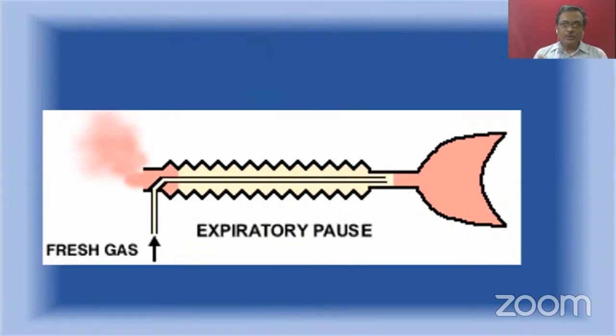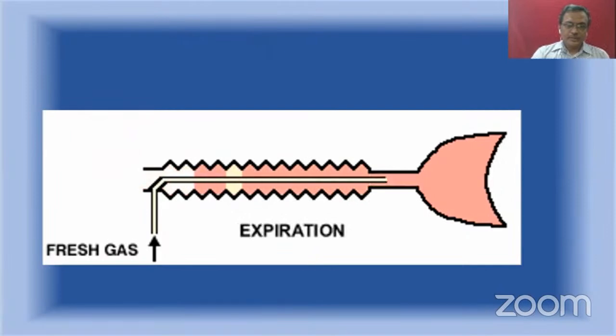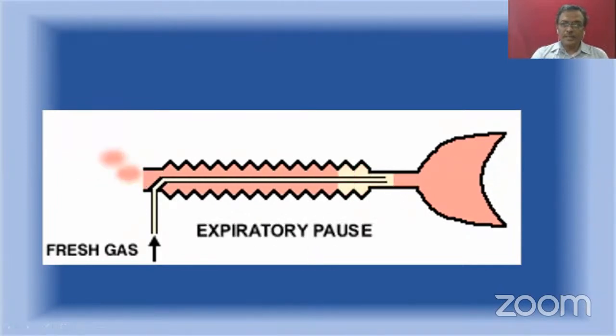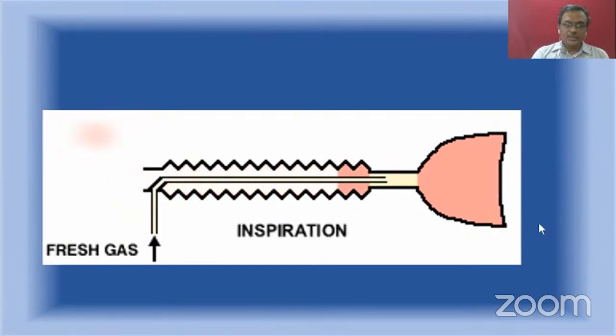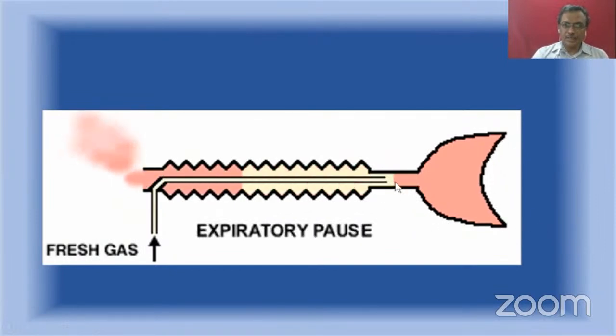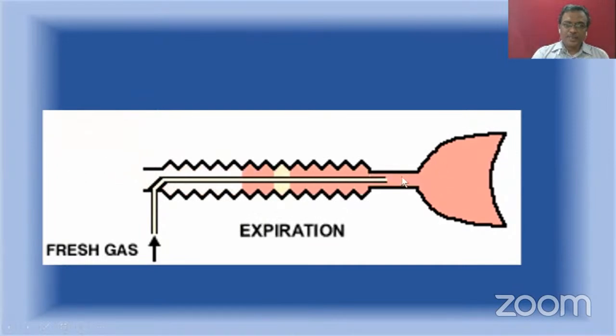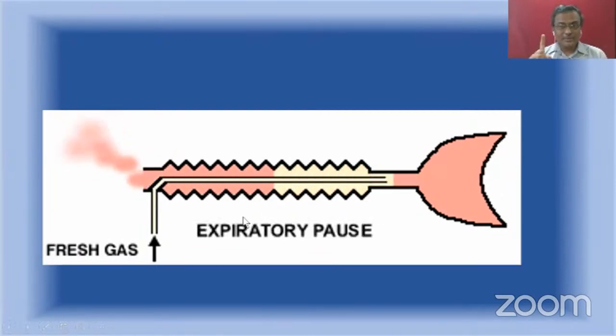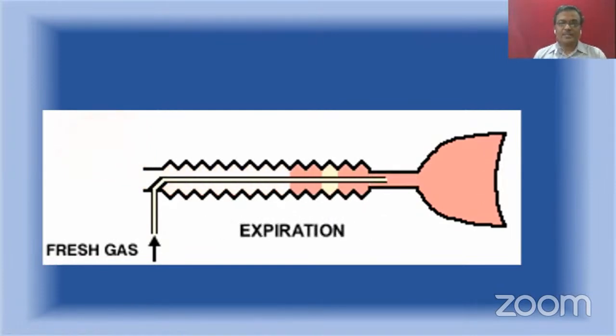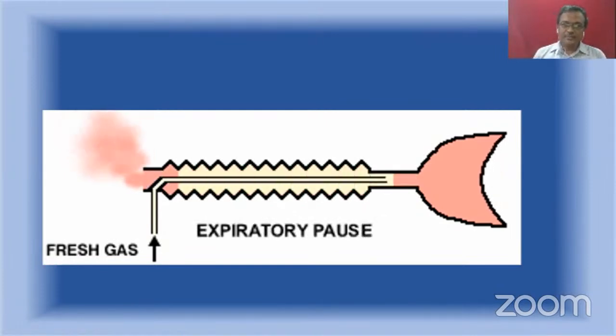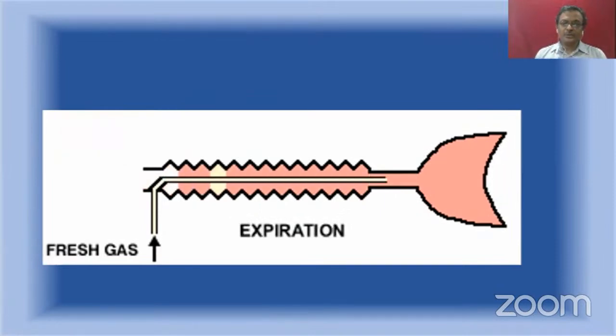And a point to be noted here is, look at this point. Here is the point where the inner tube ends, and through this tube, the fresh gas is coming out. So the expired gas is always mixing with the fresh gas coming from the inner tube and going towards the reservoir bag and valve. That's a very important point. There is always a mixing up of expired gas and the fresh gas because the tip of the inner tube is near the patient end.